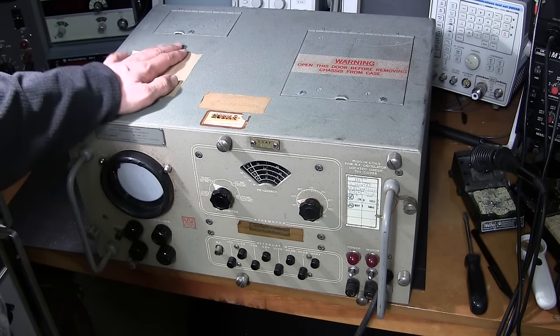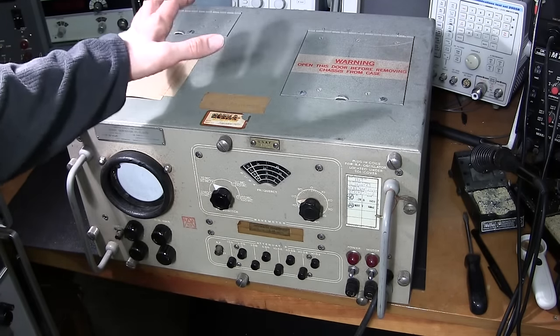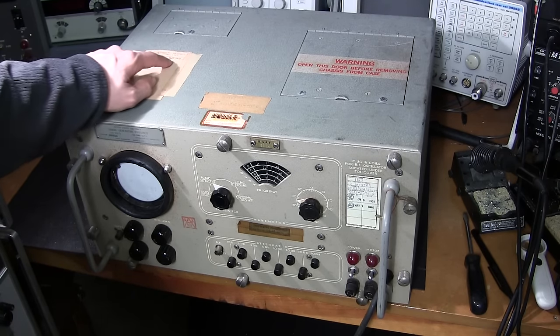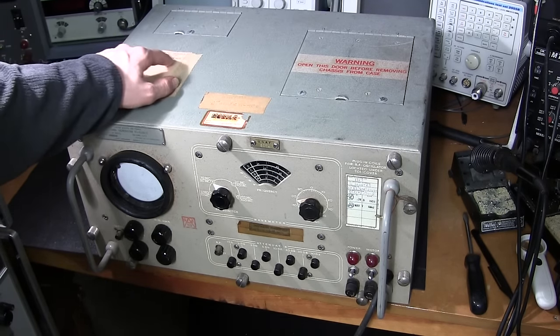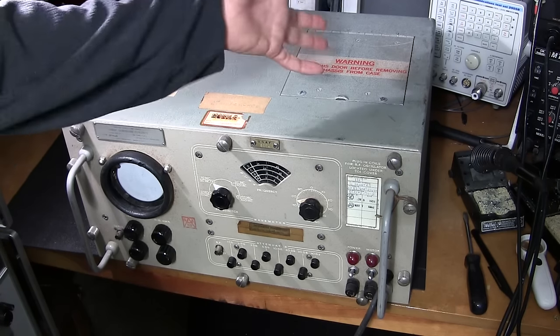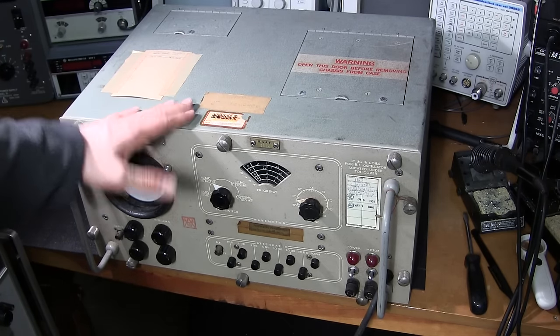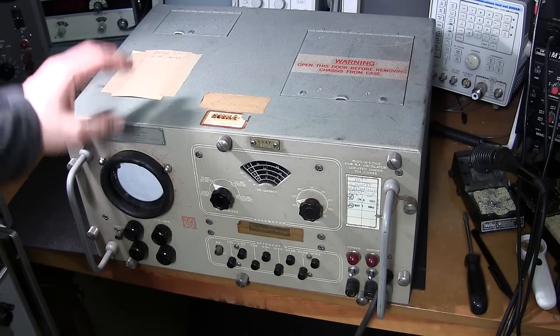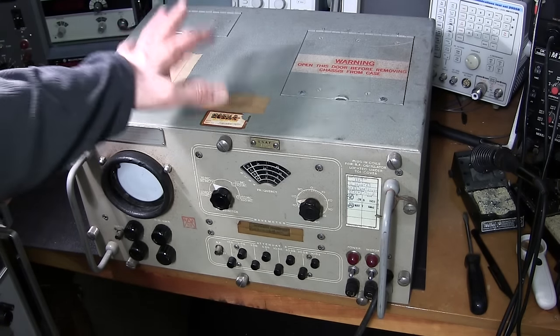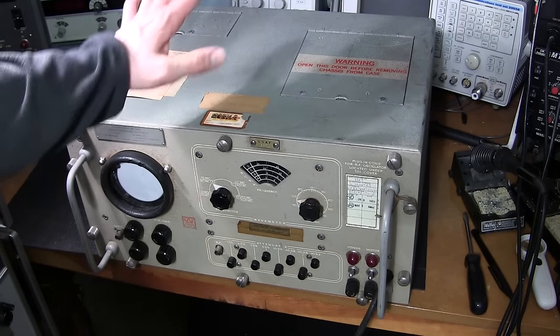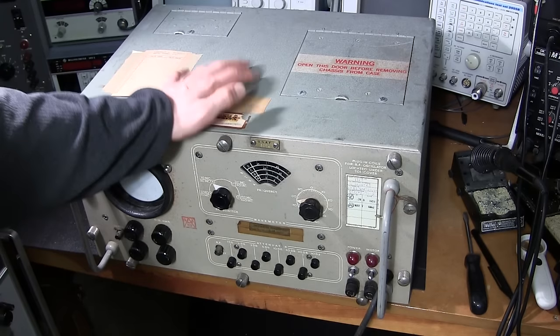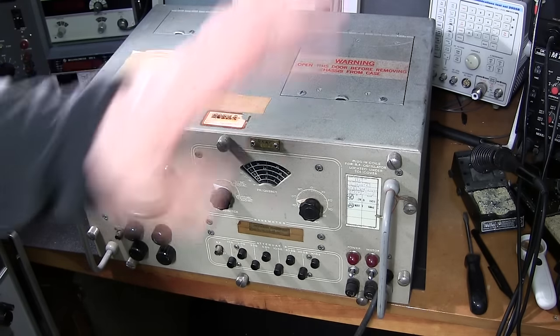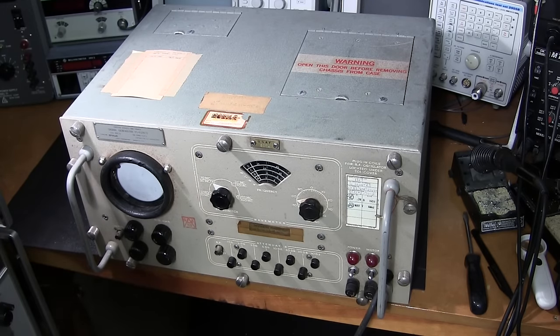Here we have a log sheet to keep an eye on who used this thing. They had to put the date used and the person that was using it had to put his last name, so if an alignment went awry or if this machine failed they could trace it back to the person who was using it and maybe even the piece of equipment that this thing did an alignment on. Obviously if this thing is out of alignment, the thing that this is aligning will also be out of alignment, so you need to keep a really close tab on that.